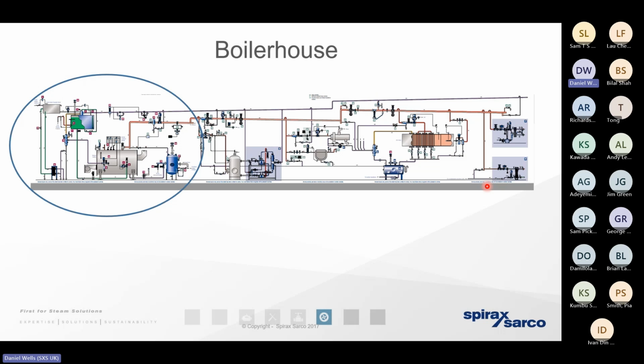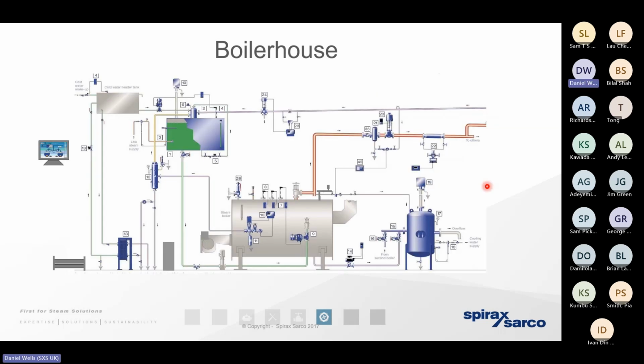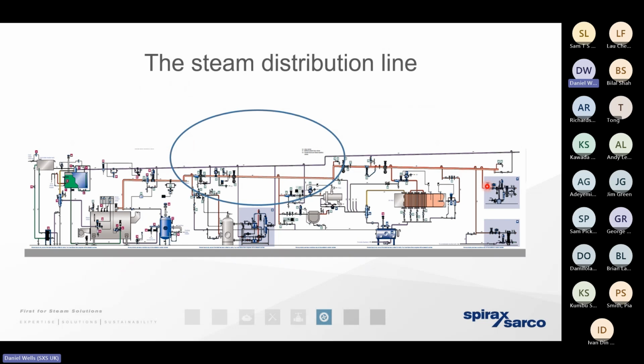Remember, we want the steam to be as dry as possible going into the pipework to reduce the burden of maintenance and to ensure that we're not having too much of a heat loss in the infrastructure, but also to ensure that the steam is very dense with energy so we can ensure that the process is taking place as efficiently as we can, what could be thousands of meters away. So we remember all of those controls and ancillaries that we discussed, the level controls, the blowdown controls, and most importantly of all, keeping the water in storage at a nice high temperature so that we can achieve all of those things.